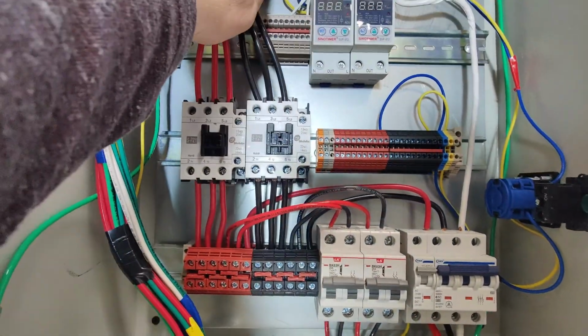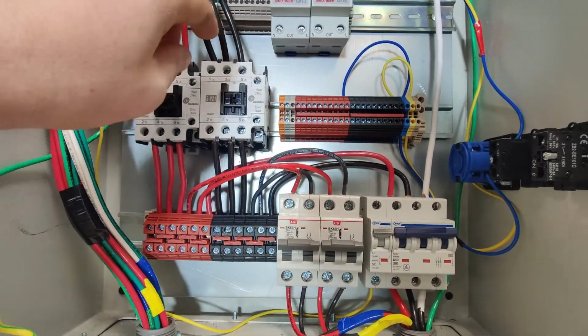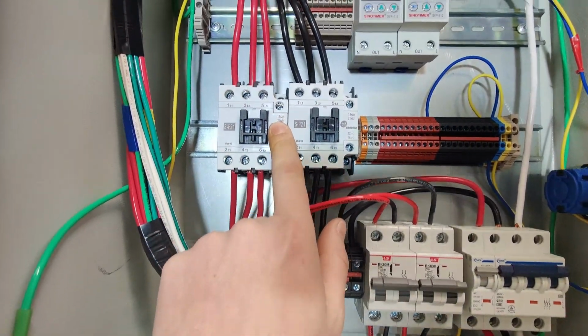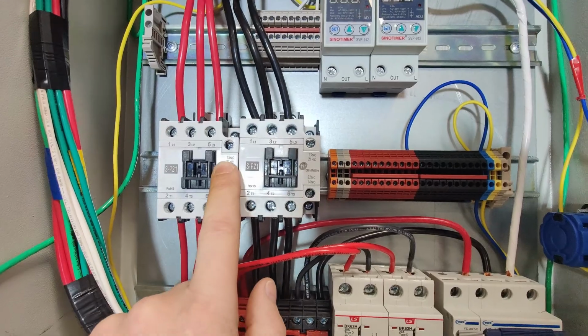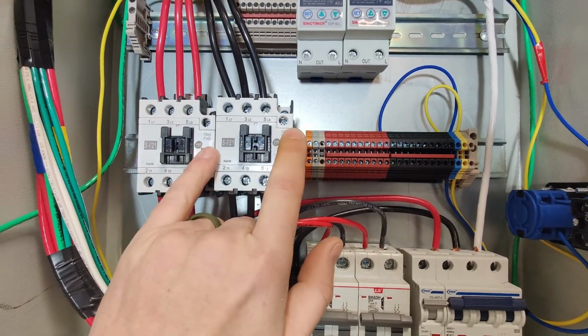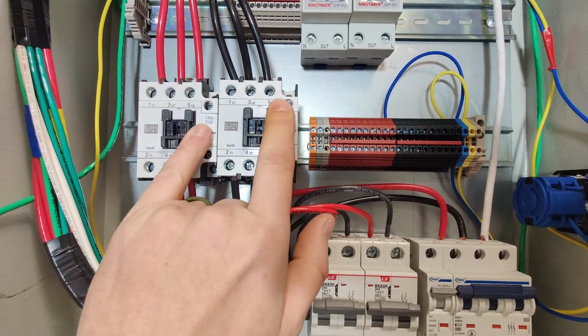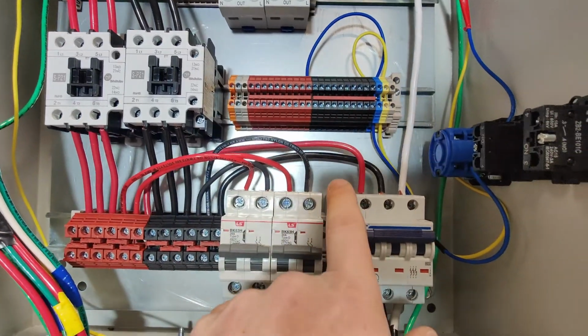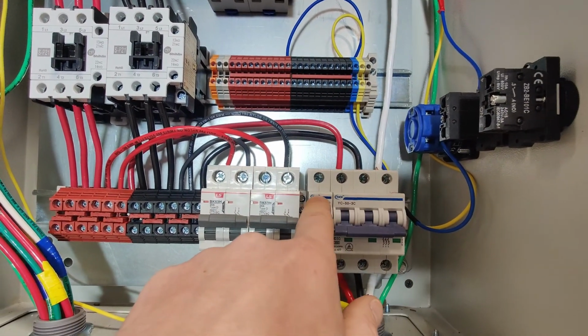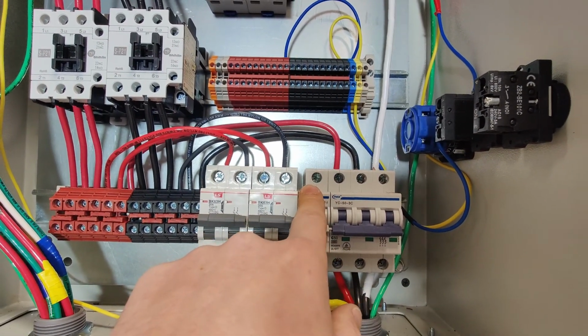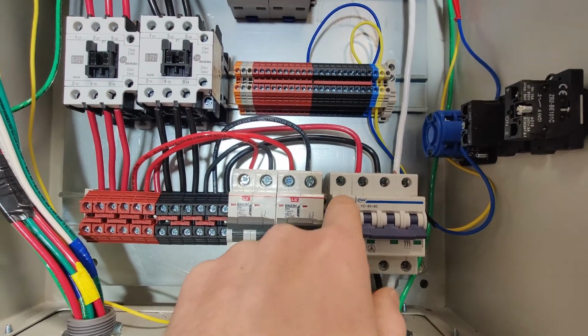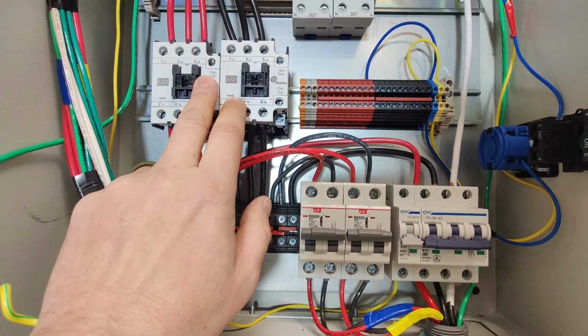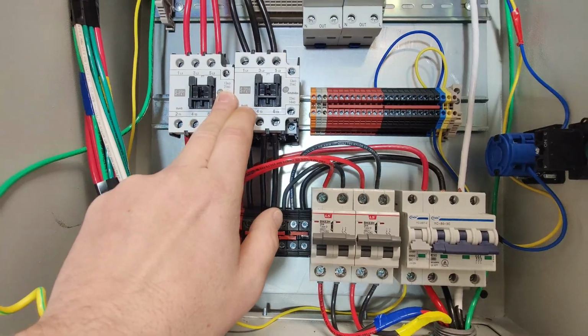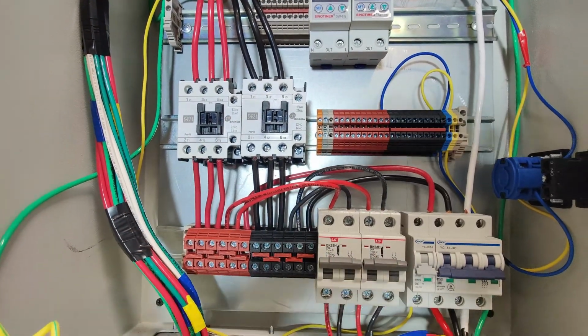So we've got this one side wired directly into the hot leg, and then out of the other hot leg, what we're going to do is come directly down to the NC side of our contactors. So if either one of these contactors closes, it's going to send a 220 volt signal to my shunt trip and kill this breaker. So let's go ahead and get the other leg wired up through the NC side of our contactor.